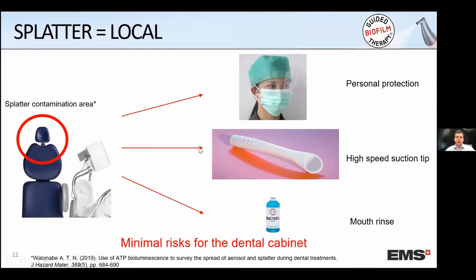Just one remark to the high-speed suction tip: we have different wording — high vacuum suction, high vacuum evacuator, high volume evacuator, high-speed evacuator or suction. All these mean the same. In fact, what is happening is not that we have high vacuum, but we have a high air flow rate. Due to this high air flow rate, we are able to suck out and take away most of the contaminated substance from the mouth.